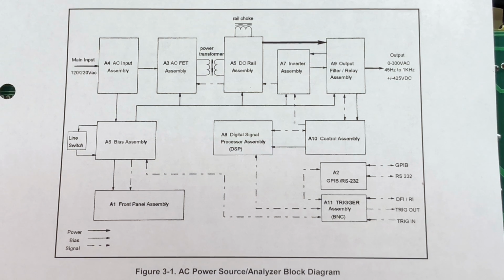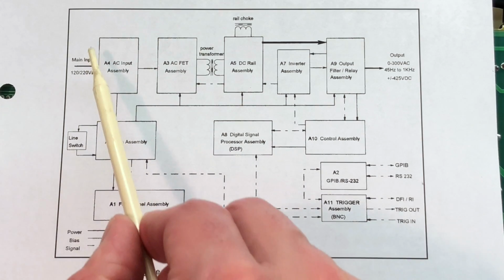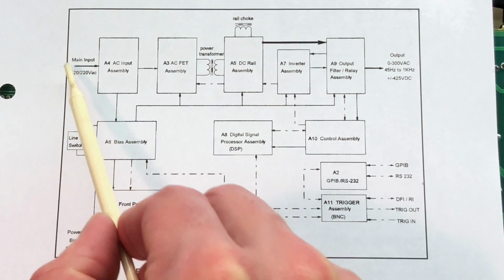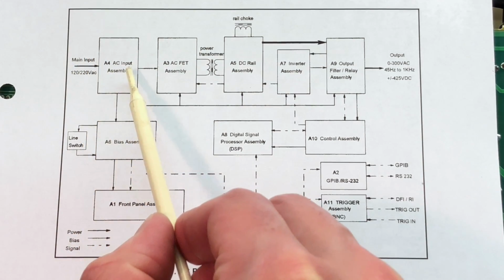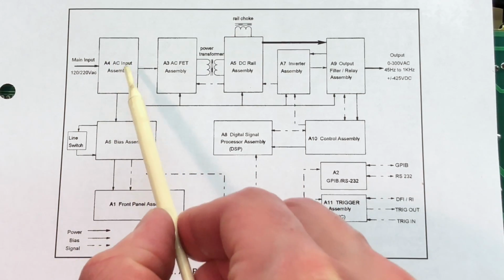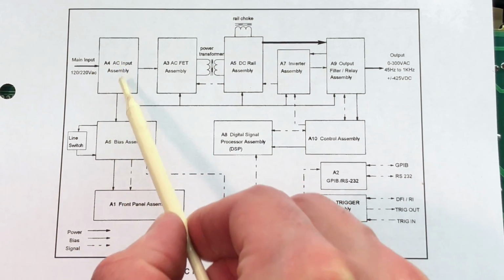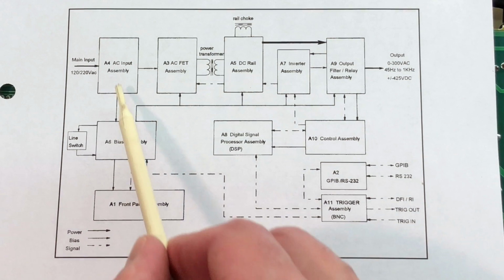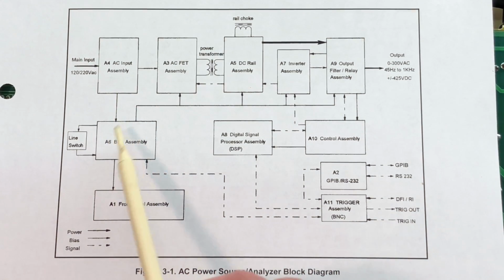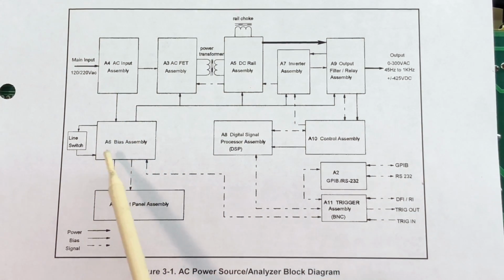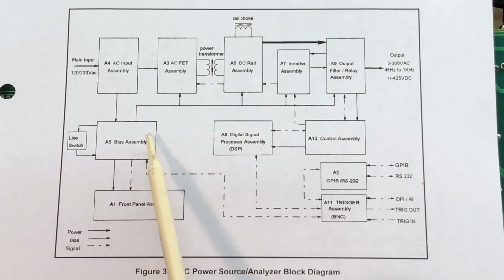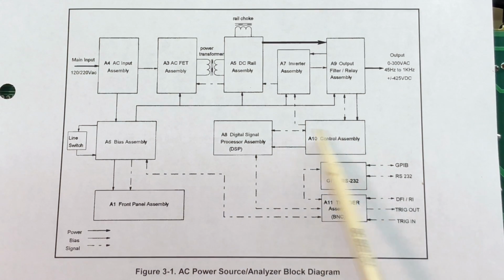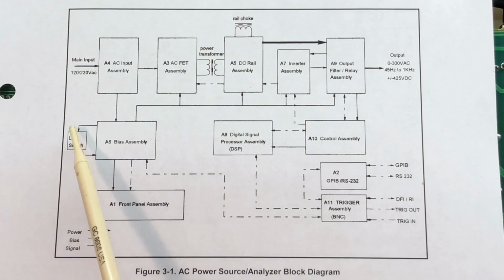Here's the block diagram for the 6812B AC power source. Starting in the upper left-hand corner, we can see the main AC input, and that AC line voltage is applied to the AC input assembly. There's two things that happen here. The AC line is applied down here to the bias assembly. This is just a 60 hertz AC line voltage coming down to a 60 hertz transformer on the bias assembly, and this is creating numerous DC voltages within the instrument just to power all of the support circuitry. See the line switch right here is affecting the bias assembly as well.